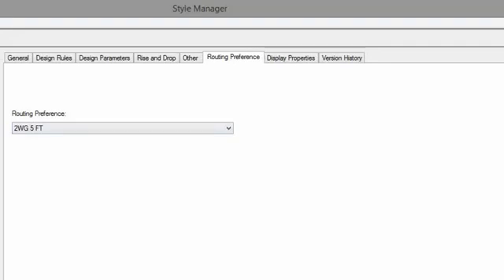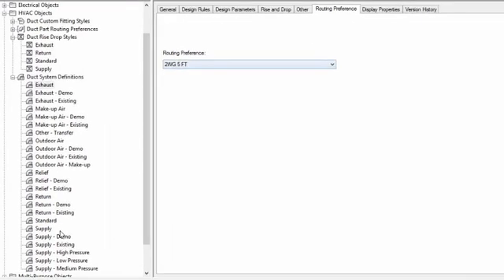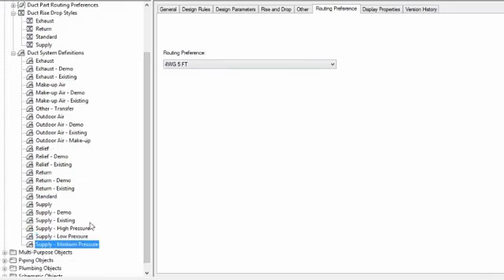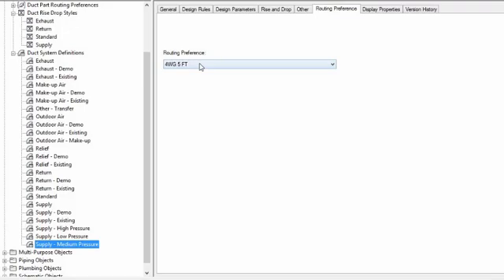Routing preference. This is where you would set up the routing preference to go along with your system. So when I switch systems, when I switch to running the exhaust system, my routing preference is going to automatically switch to my 2-inch water gauge. When I go down to my supply low pressure, you can see that my routing preference is also 2-inch. When I select my medium pressure, you can see that it switches to 4-inch. You are of course free, and we recommend that you change that routing preference to your own if you happen to change the out-of-the-box naming scheme. It will certainly help with your routing of duct.